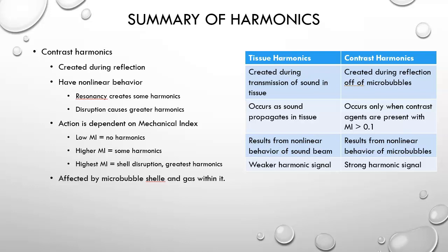The resonance creates some harmonics, and disruption of the contrast will create even greater harmonics. This action is all dependent upon the mechanical index, so at low mechanical index between 0 and 0.1 you get no harmonics.